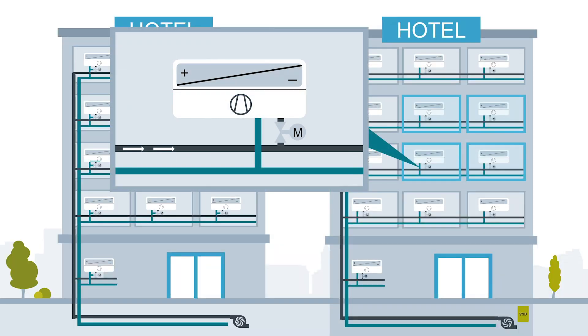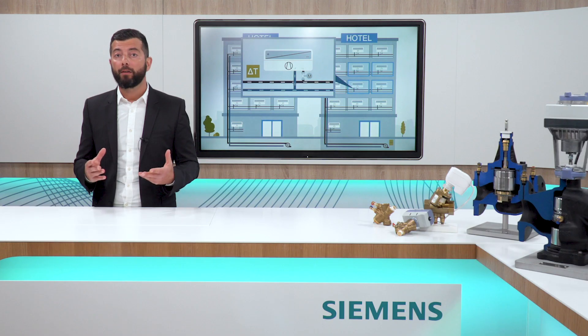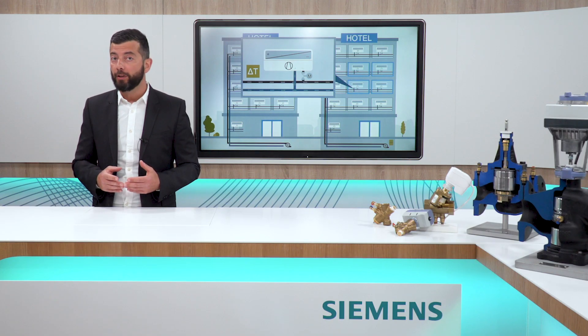In the system on the right, the PICV adjusts the flow to the demand so that the delta T remains consistently high and, thanks to the pump speed control, much less energy is required and the efficiency of the system remains high. That's why, for hydronic flow optimization, I always recommend dynamic valves, no matter which building automation system is used.